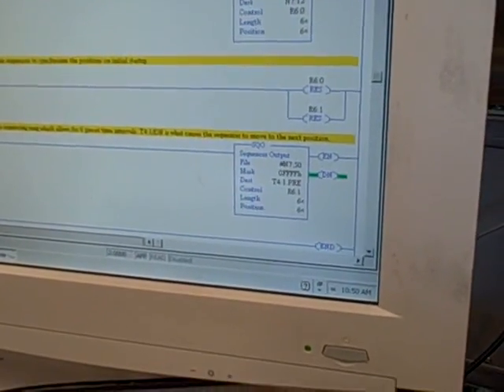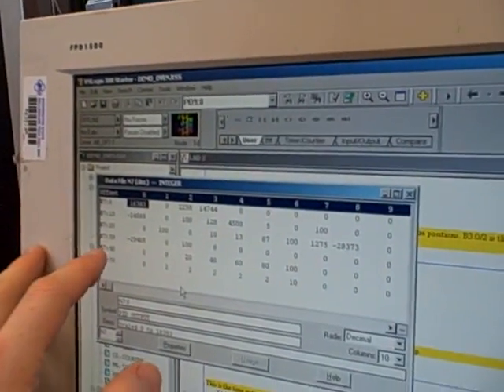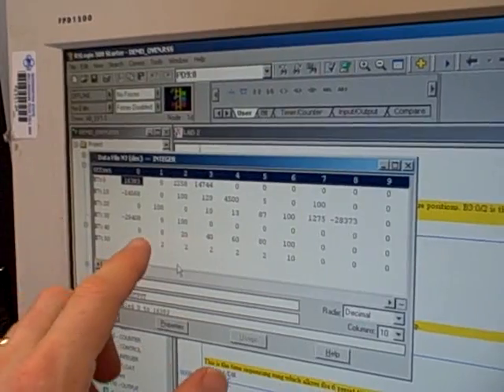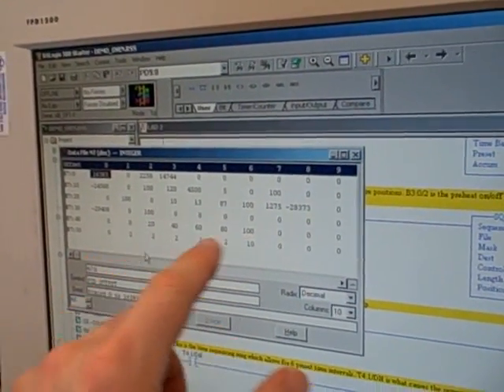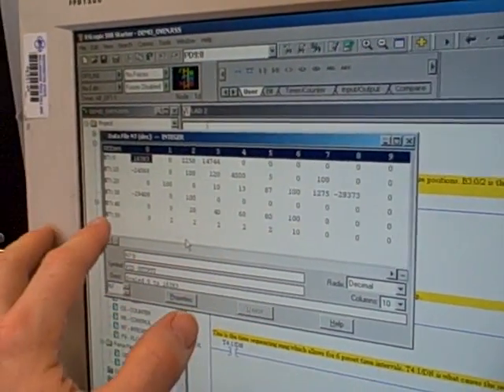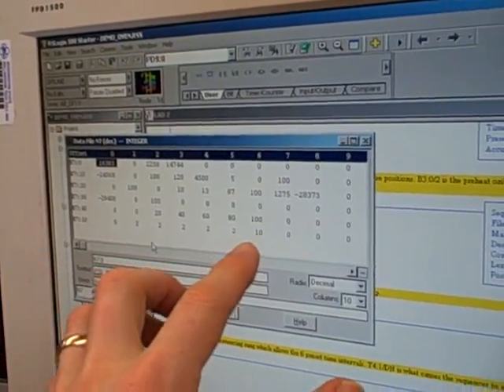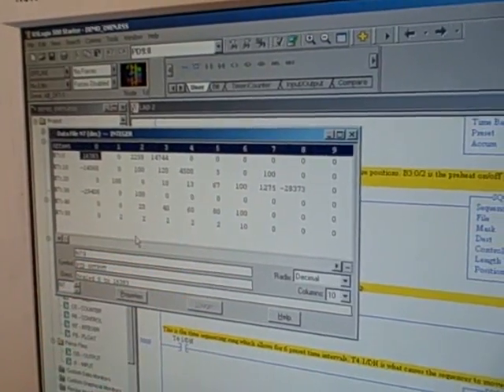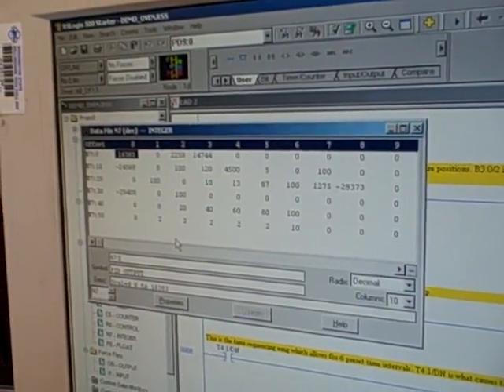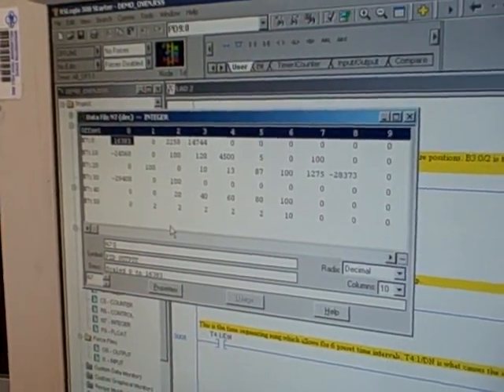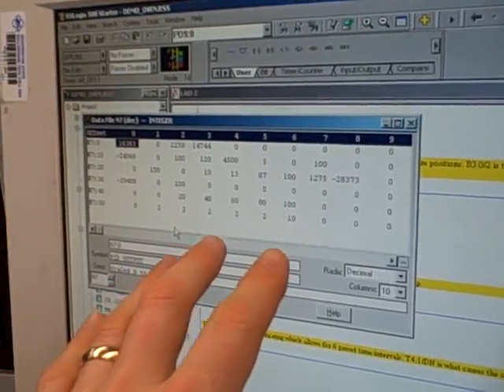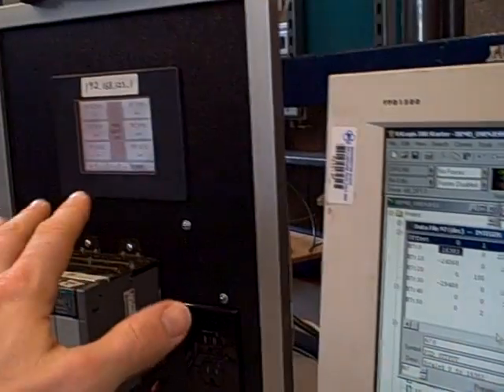So if we go over here to N7, we can see it's actually N7 colon 40, these are the six registers for different temperatures, and N7:50 here, these are the six registers for the time durations, and those values again are written by the entries over here on the HMI.